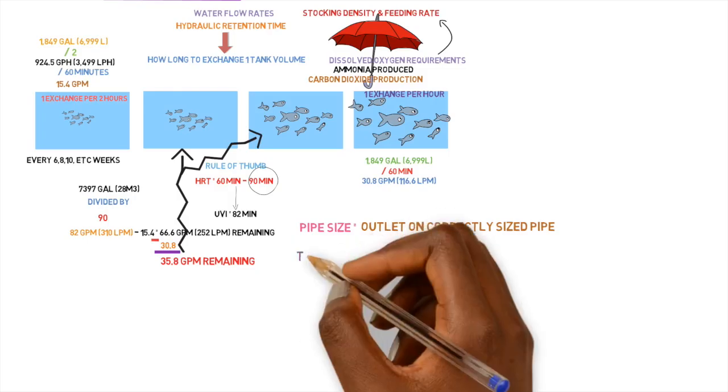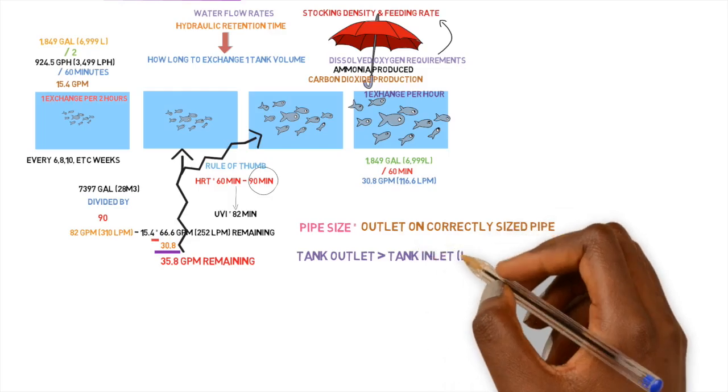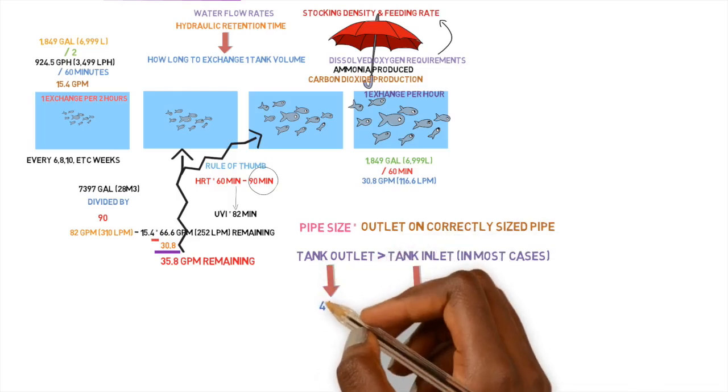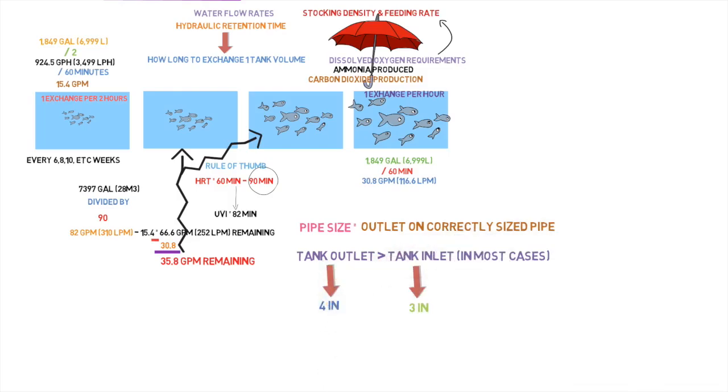And for the outlet, of course, the outlet cannot be the same size as the inlet. So if your inlet is three inches, and that's how much is being supplied in there, then your outlet is going to have to be bigger because the gravity does not accept the same amount of flow as a pressurized pipe. Pressurized pipe can push out way more volume in a three inch pipe than what gravity can accept in a three inch pipe.